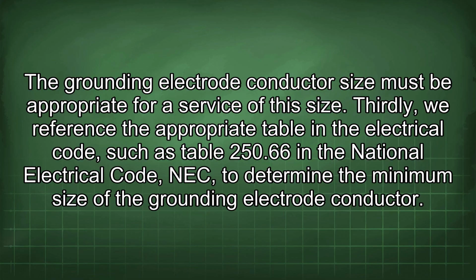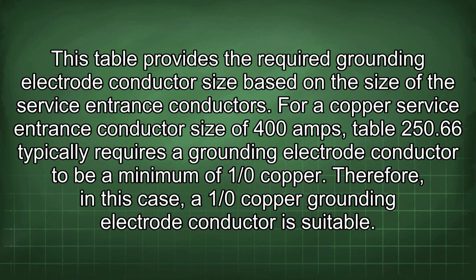Thirdly, we reference the appropriate table in the electrical code, such as Table 250.66 in the National Electrical Code, NEC, to determine the minimum size of the grounding electrode conductor. This table provides the required grounding electrode conductor size based on the size of the service entrance conductors. For a copper service entrance conductor size of 400 amps, Table 250.66 typically requires a grounding electrode conductor to be a minimum of 1/0 copper. Therefore, in this case, a 1/0 copper grounding electrode conductor is suitable.